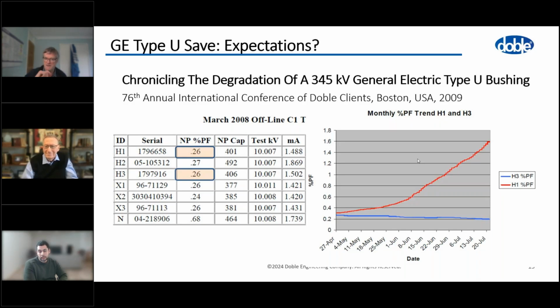But on the right-hand side, you can see the online power factor, and this is just a relative power factor system. There was no reference voltage to do any confirmation. It is quite high for an offline test, but in an online system, this is not unusual. But the level at which it got to was the point which was decided right at the outset: when it reaches here, we take it out. And they did the full forensics, and they confirmed that there was a problem with contamination in the bushing, which was leading to deterioration of the power factor.